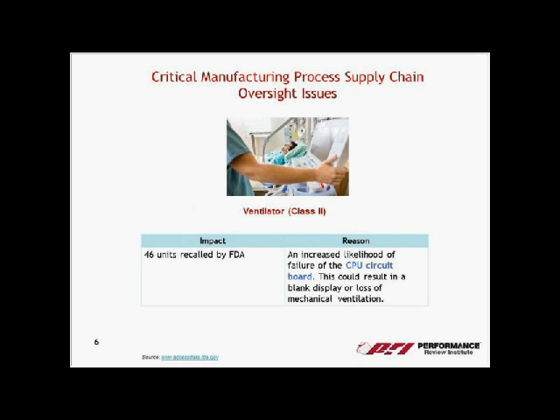The second one is a ventilator, Class 2, with 46 units recalled by the FDA, and the defect was in a CPU circuit board. That defect could result in the display going blank or loss of mechanical ventilation. Again, it points to a critical process that wasn't performed properly.